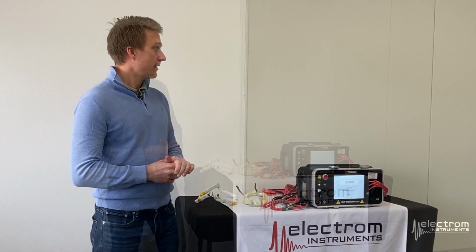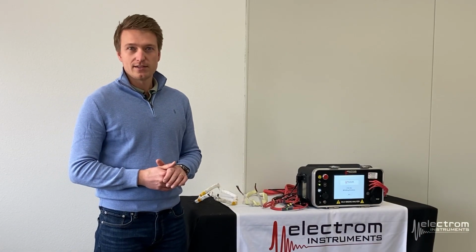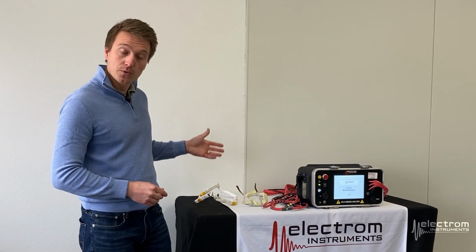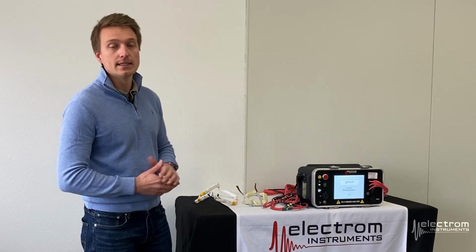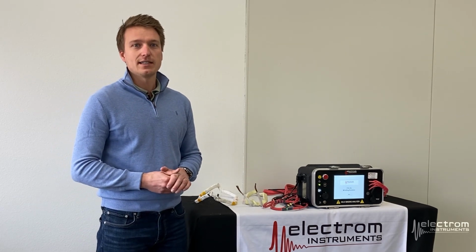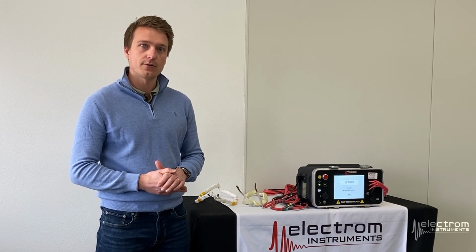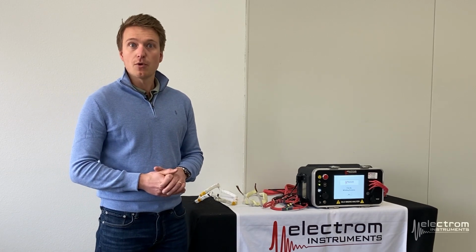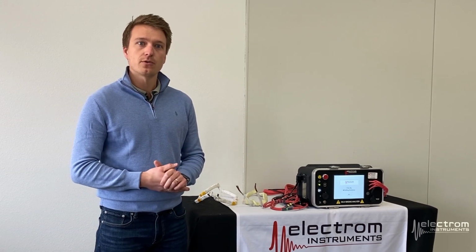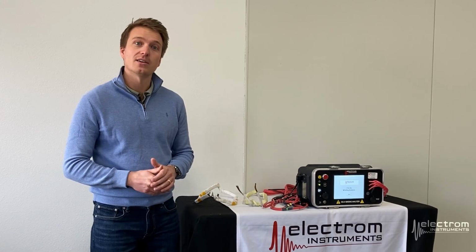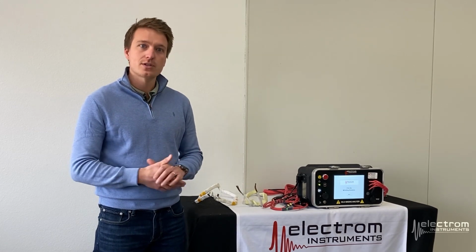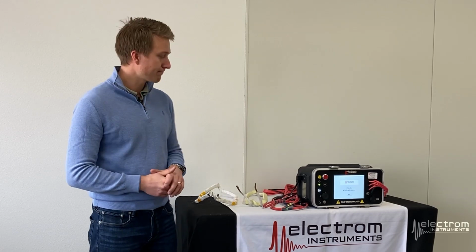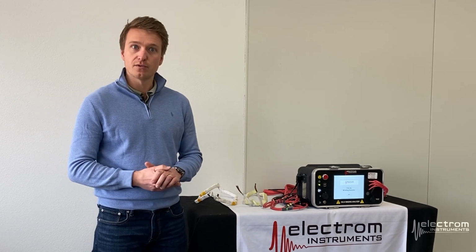Expect to see a couple of differences just due to the shape and size differences, but they're both known good coils in general. The advanced multi-coil test feature and reporting is used for testing form coils in a bench or laboratory setting, and also for testing coils after insertion in the stator slots. We also use the same software for testing on DC motors, more specifically DC armatures. So if you do bar-to-bar surge testing on the commutator, or span surge testing on the commutator, or winding resistance measurements bar-to-bar on the commutator, the same software is used for that purpose.